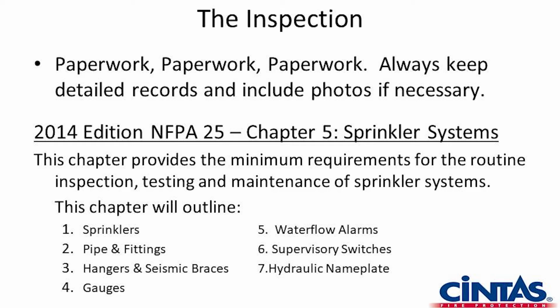And then supervisory. What we're talking about is a valve required to be supervised, locked and chained, or both. Sometimes it's just secured with lock and chain. In many different circumstances, AHJs play a big part in how a valve is protected. Obviously, the best method would be for it to be supervised and locked and chained. That's not always feasible, but that's one of the things covered in Chapter 5.